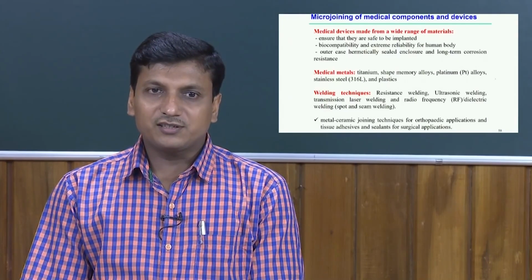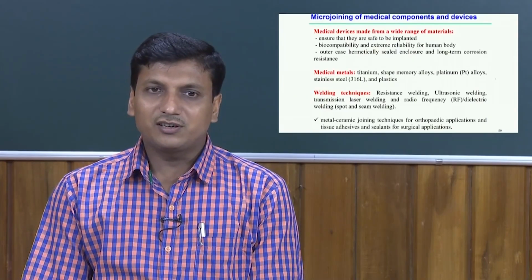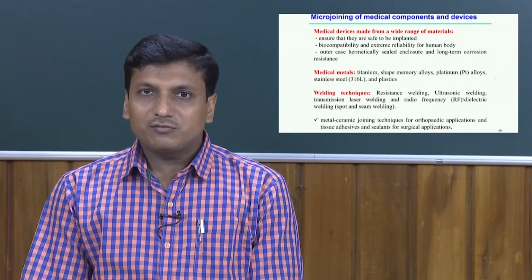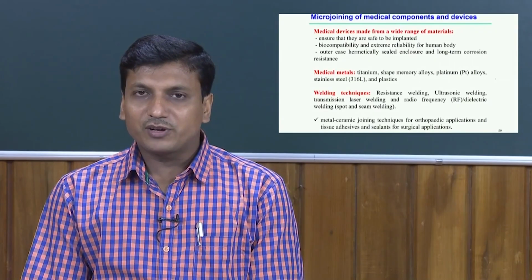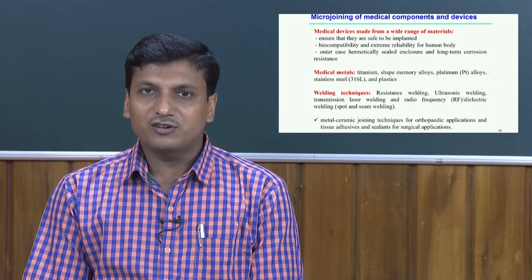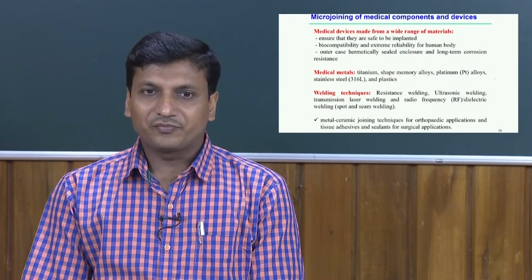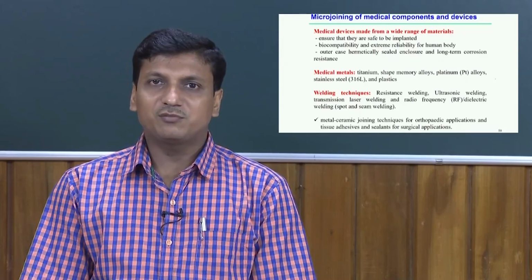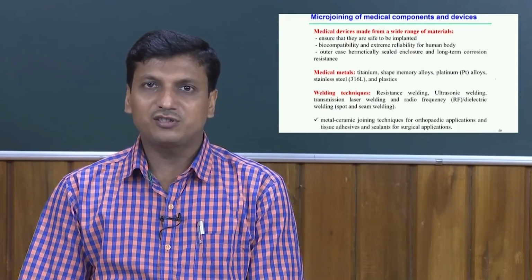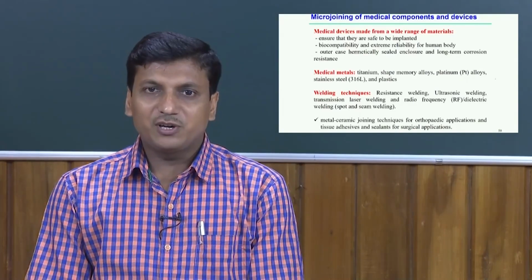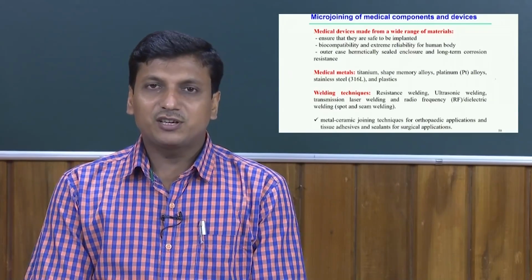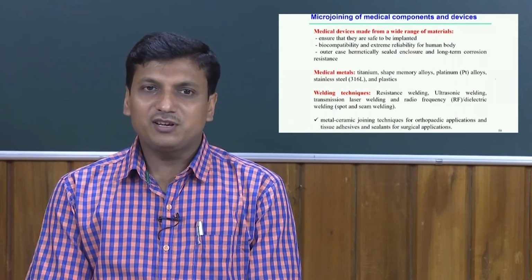In most cases we use a hermetically sealed enclosure, and the material should have the characteristic of long-term corrosion resistance. These are the typical requirements for the application of any kind of processing technology, specifically for medical devices.